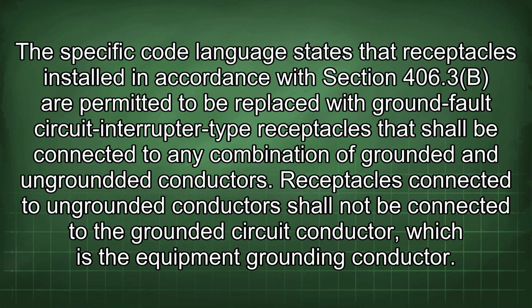406.3(D)(2). This specific code language states that receptacles installed in accordance with section 406.3(B) are permitted to be replaced with ground fault circuit interrupter type receptacles that shall be connected to any combination of grounded and ungrounded conductors. Receptacles connected to ungrounded conductors shall not be connected to the grounded circuit conductor, which is the equipment grounding conductor.